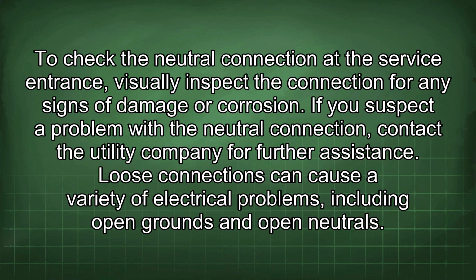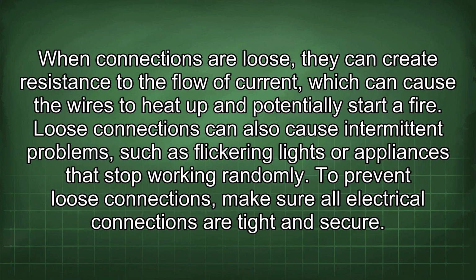Loose connections can cause a variety of electrical problems, including open grounds and open neutrals. When connections are loose, they can create resistance to the flow of current, which can cause the wires to heat up and potentially start a fire. Loose connections can also cause intermittent problems such as flickering lights or appliances that stop working randomly.